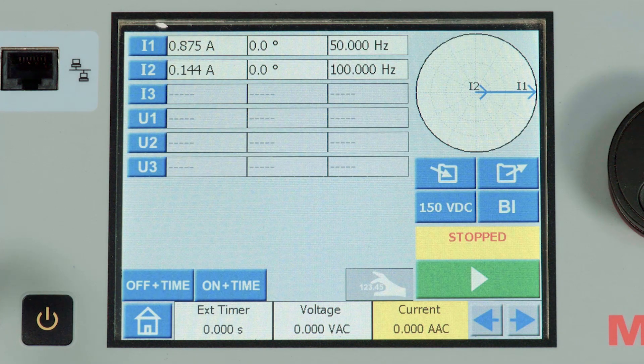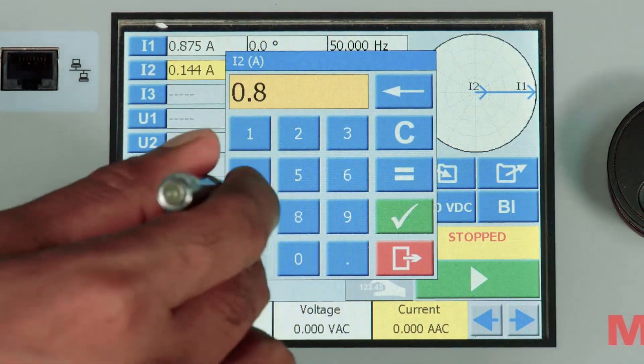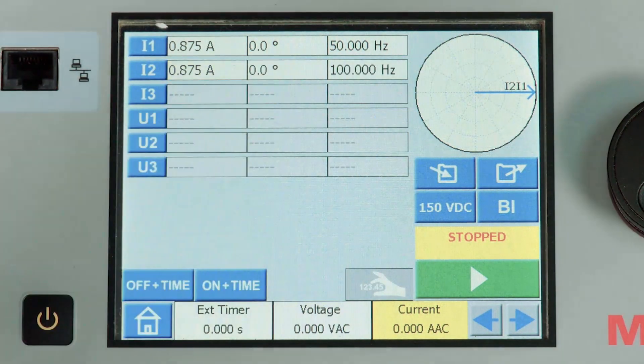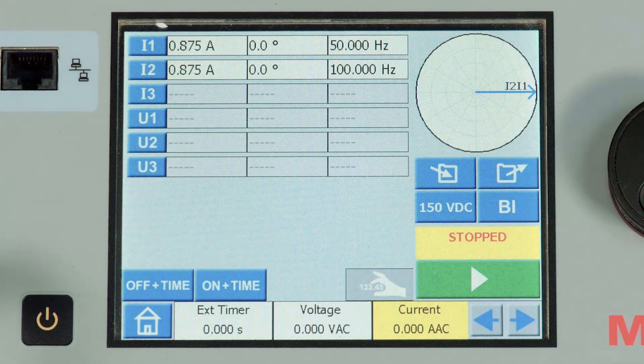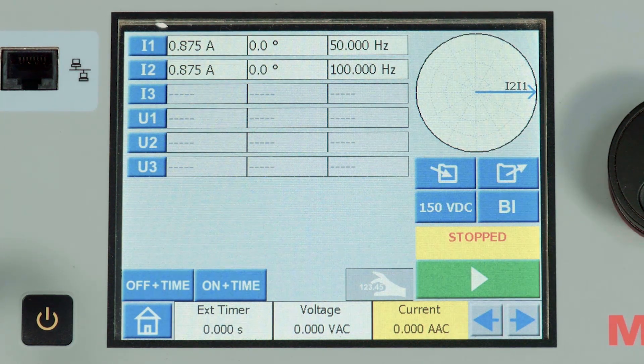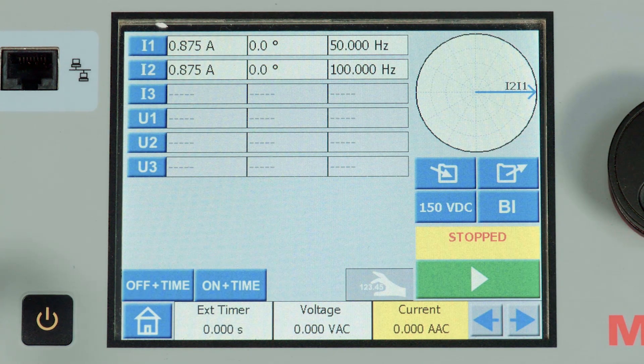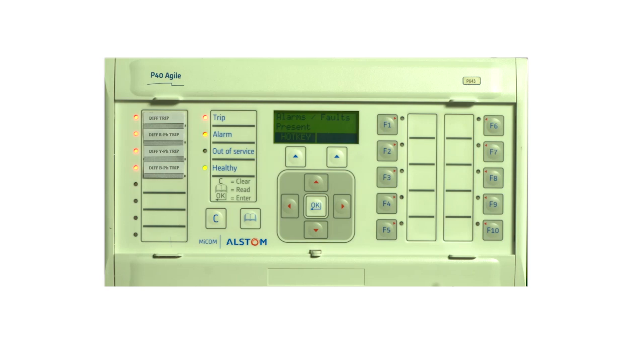Let us verify the non-operate-to-operate method. In this method, we will inject 0.875A at 50Hz in CT1 and 0.875A at 100Hz in CT2. The relay should pick up in differential. However, the tripping should not be executed.